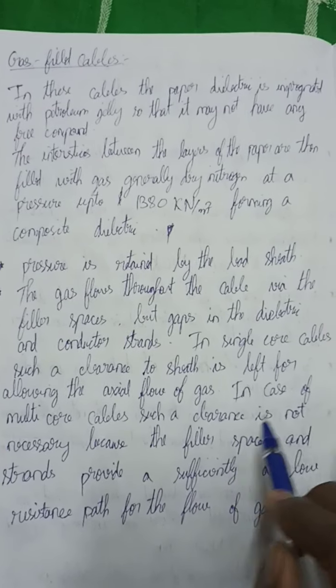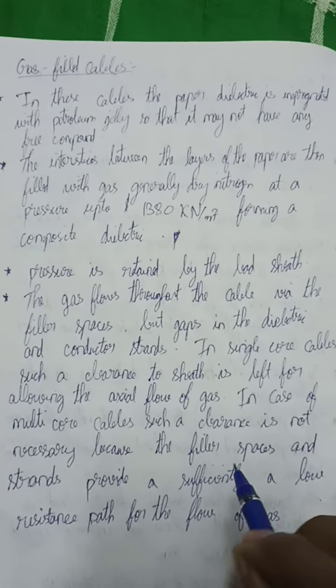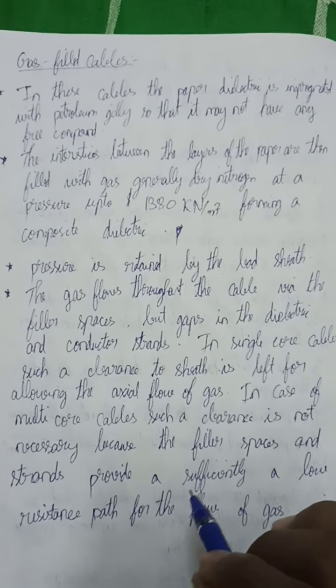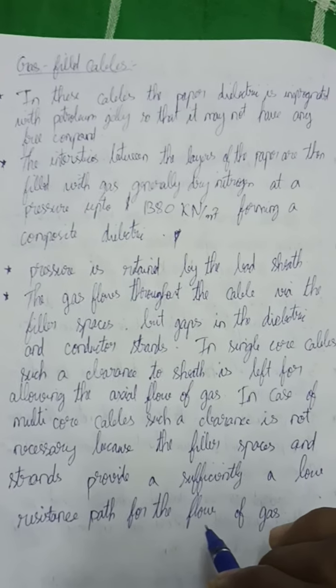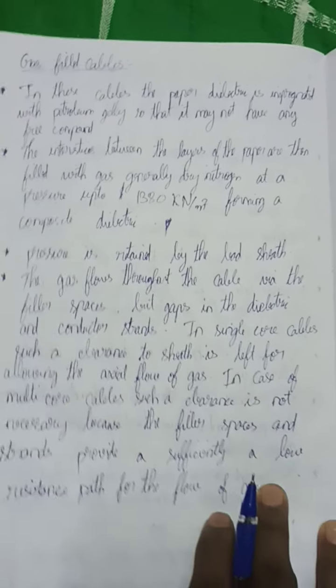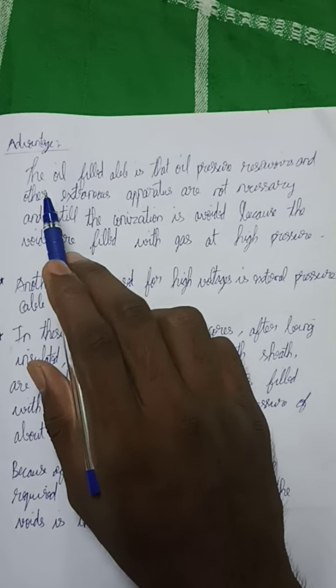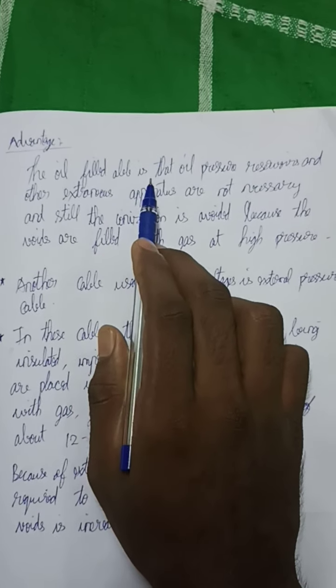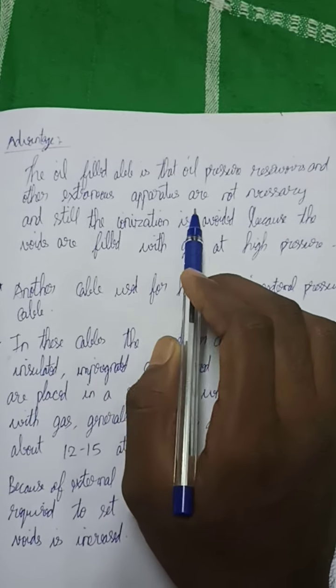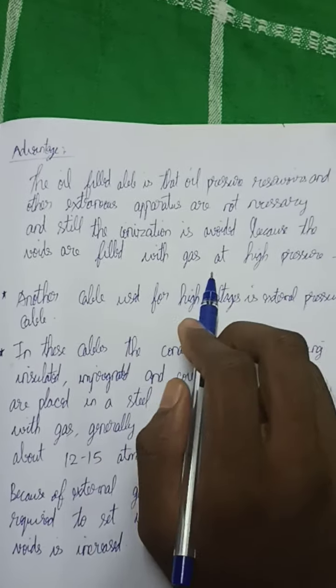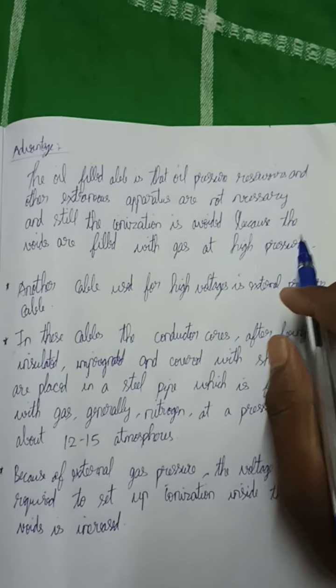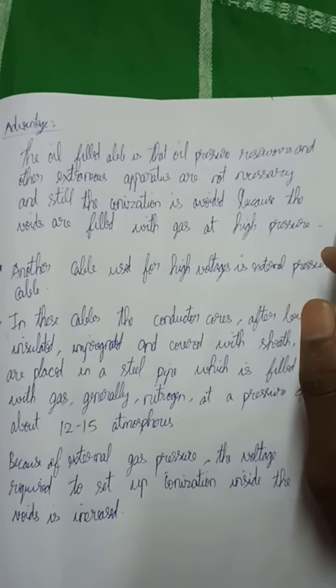In multi-core cables, such a clearance is not necessary because the filler spaces and strands provide a sufficiently low resistance path for the flow of gas. Then we go to the advantages of gas filled cables. Compared with the oil filled cable, oil pressure reservoirs and other extraneous apparatus are not necessary, and still ionization is avoided because the voids are filled with gas at high pressure. This is the main advantage of gas filled cables.